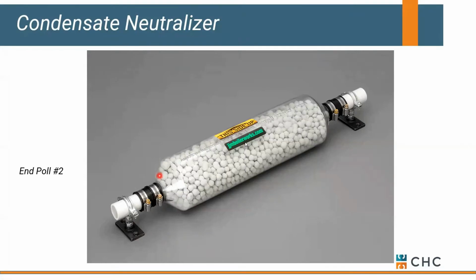Again, I would tell you they're required. It's certainly cheap insurance, so you don't tear up your floor drains or your elbows. Condensing boilers are most efficient at high fire versus low turn down. I don't think this is worded real well, and forgive me, that's on my end. They're most efficient at high fire. Condensing boilers are most efficient at low fire, okay? And then sorry, no idea. Hopefully this helps to address some of those. Again, thank you guys for taking part in the poll.